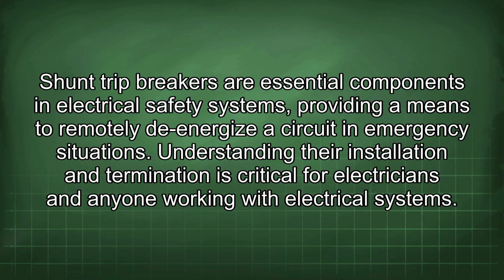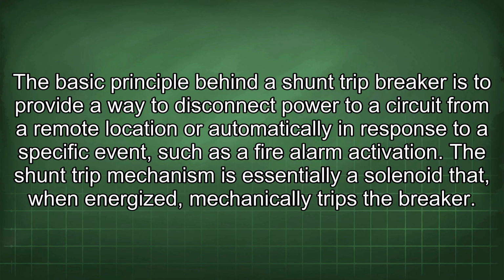Shunt trip breakers are essential components in electrical safety systems, providing a means to remotely de-energize a circuit in emergency situations. Understanding their installation and termination is critical for electricians and anyone working with electrical systems. The basic principle behind a shunt trip breaker is to provide a way to disconnect power to a circuit from a remote location or automatically in response to a specific event, such as a fire alarm activation.